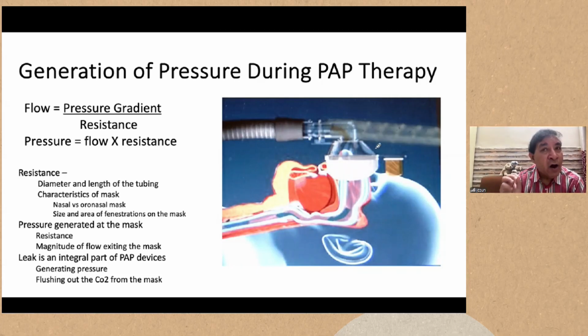essential leak or intentional leak. Because if this leak is not there, there won't be any pressure. So you need flow. This flow exits from these fenestras on the mask, and then that provides the resistance, and this results in pressure, and that pressure is transmitted into the upper airway tract.